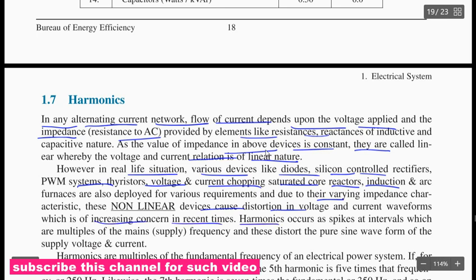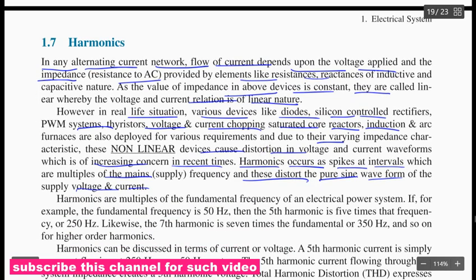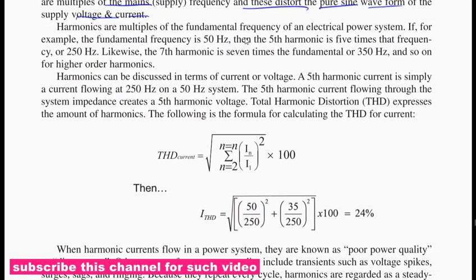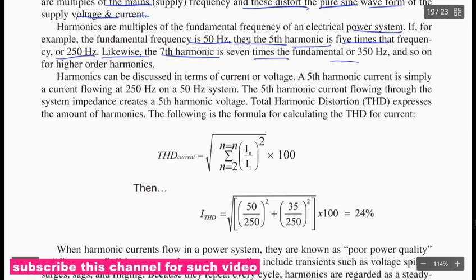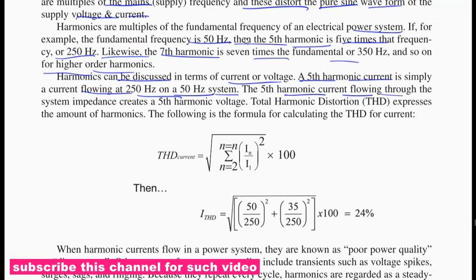Harmonics occur as spikes at intervals which are multiples of the main frequency, and these distort the pure sine wave of the supply voltage and current. Harmonics are multiples of the fundamental frequency in an electrical power system. If, for example, the fundamental frequency is 50 Hz, then the fifth harmonic is 5 times the frequency, 250 Hz. Likewise, the seventh harmonic is 7 times the fundamental frequency, 350 Hz, and so on for the higher order harmonics. Harmonics can be discussed in terms of current and voltage. The fifth harmonic current is simply a current flowing at 250 Hz on a 50 Hz system. The fifth harmonic current flowing through the system impedance creates a fifth harmonic voltage.